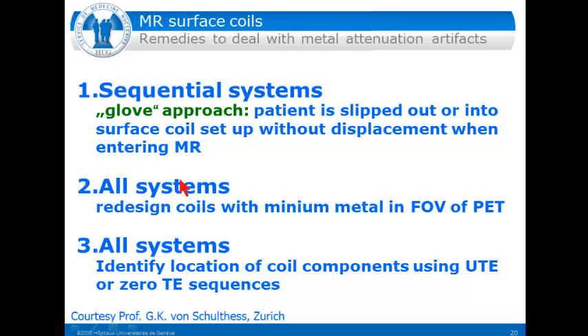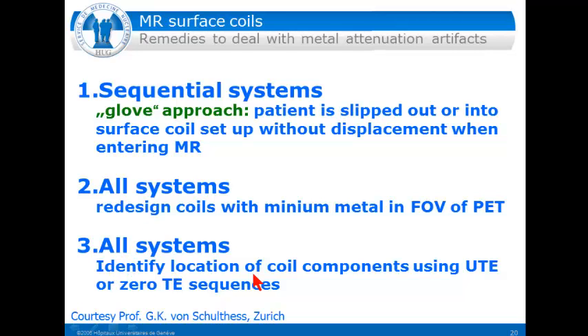Regarding surface coils — this is also a problem I'll discuss later. Sequential systems use a glove approach so the patient is slipped into or out of the surface coil setup without displacement when entering the MR. In all systems, vendors had to redesign the coils with a minimum of metal in the PET field of view to avoid attenuation artifacts from metal parts, and the coils must be kept small enough since there is also some attenuation from plastic. MR doesn't see the coils, so this must be accounted for in attenuation correction.